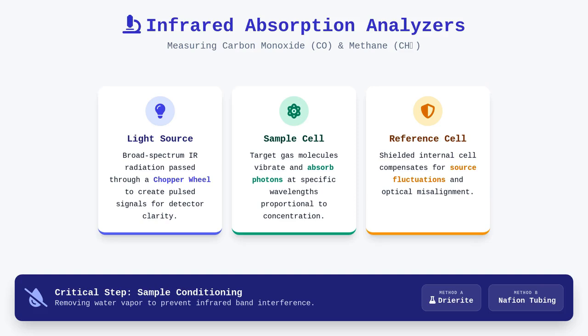Infrared absorption analyzers serve as the backbone for measuring carbon monoxide and methane, operating on the fundamental principle that these gases absorb electromagnetic radiation at specific wavelengths. The device uses a broad-spectrum light source passed through a sample cell, where the target gas molecules vibrate and absorb photons proportional to their concentration.